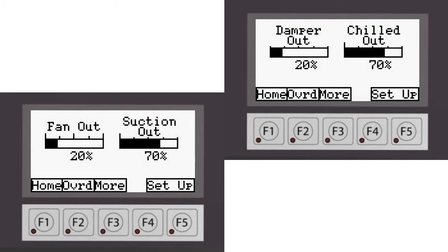The fan output is a function of the dry bulb temperature in the room and the suction or chilled output is a function of the dew point in the room.